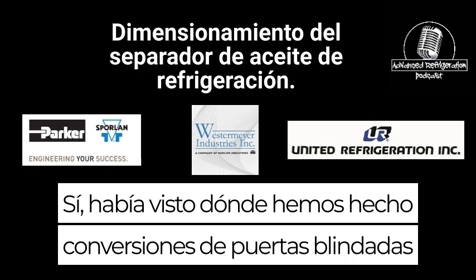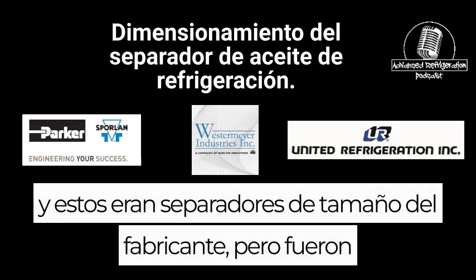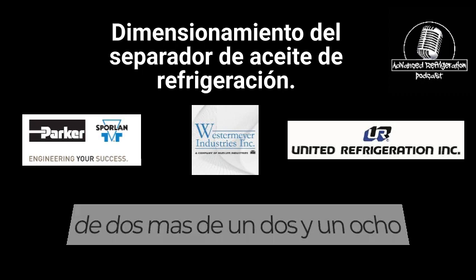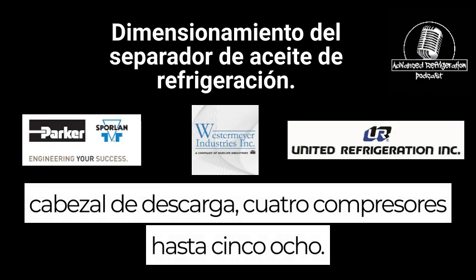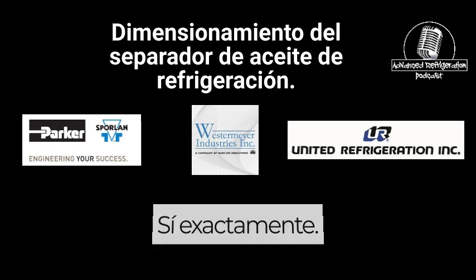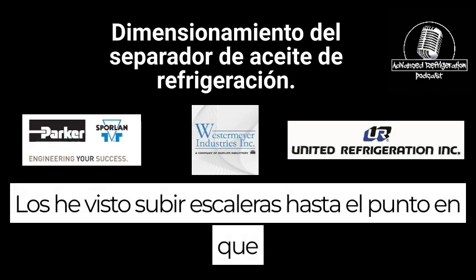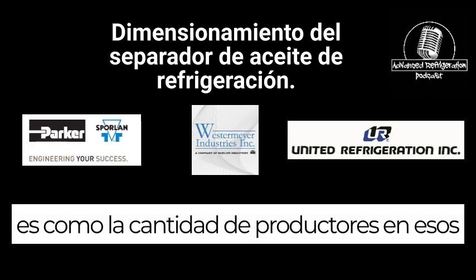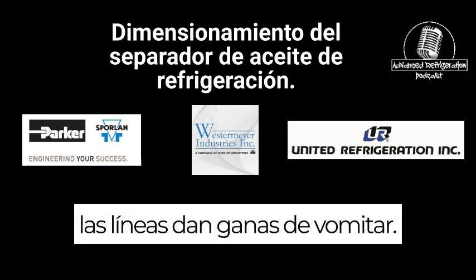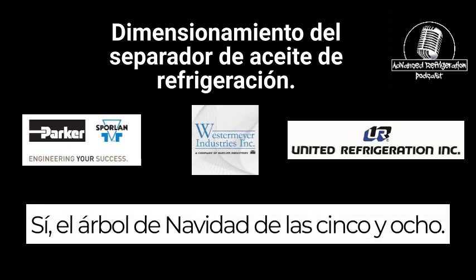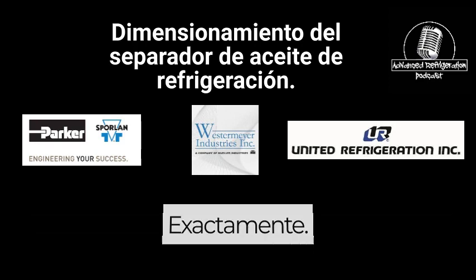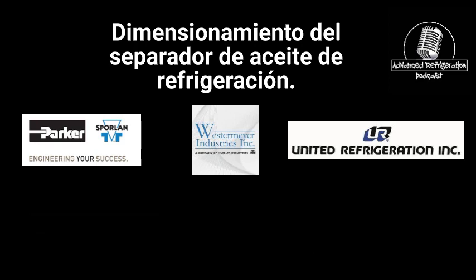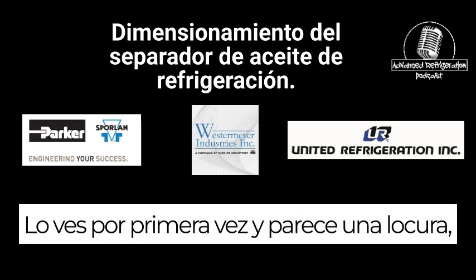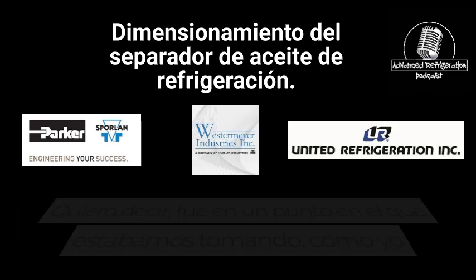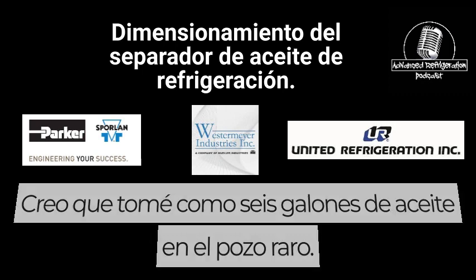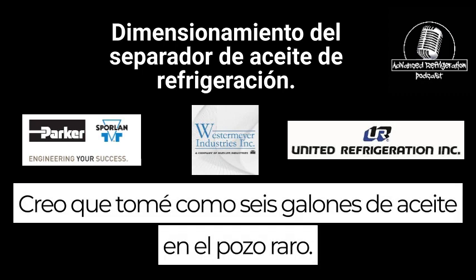Yeah, I've seen where we've done blast door conversions, and these were manufacturer size separators, but it went from a 2 1/8 discharge header, with 4 compressors, down to 5/8. Yep, exactly. I've seen them stair stepped to the point where the amount of restrictions in those lines makes you want to vomit. They had the Christmas tree from 5/8 to 2 1/8. When you first see it, it looks insane, but it works. It was at a point where I think I took like 6 gallons of oil out of the rack.